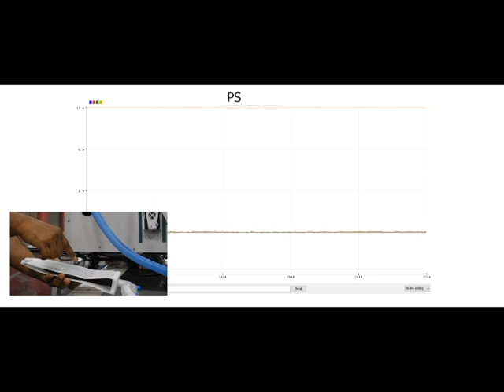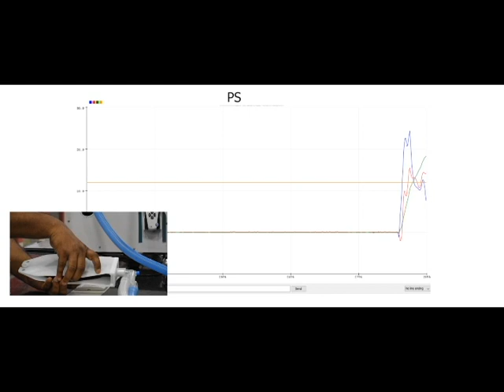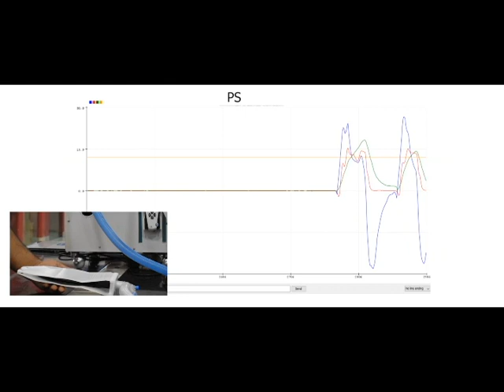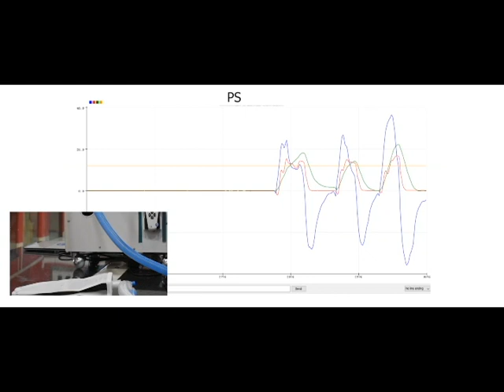So let's start the ventilator now in pressure support mode. You can see that the ventilator is not giving mandatory ventilation, but whenever the patient tries to take his own breath, it supports it at the given pressure support setting. Let me show you how it is doing. You can see that I am giving my own breath and it is being supported by the ventilator continuously, so that it gives the ventilation here. It maintains that constant pressure, and finally the pressure support is achieved.